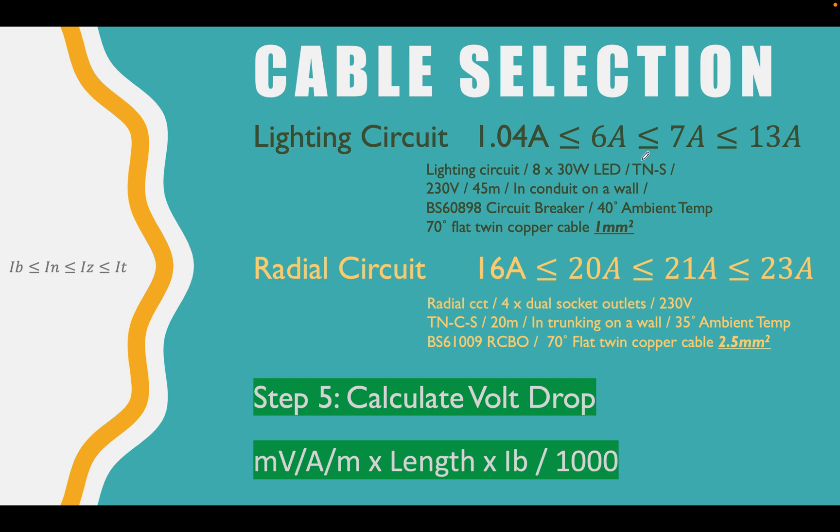So we've calculated our design current for each, we've selected our protected device rating, we've calculated our IZ, and we've checked that it's lower than the IT, the tabulated value.